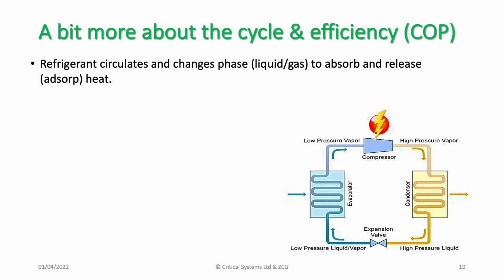So the refrigerant circulates in the direction shown in this diagram. So it's rotating clockwise. And the key components of the system are the compressor, the condenser, the expansion valve, and the evaporator. And the refrigerant passes through each of those components. If we start at the compressor, it sucks in refrigerant vapor and compresses it by doing mechanical work driven by an electric motor. That compressed vapor rises in temperature and it passes through the condenser where it is cooled and rejects the heat to our heating system.